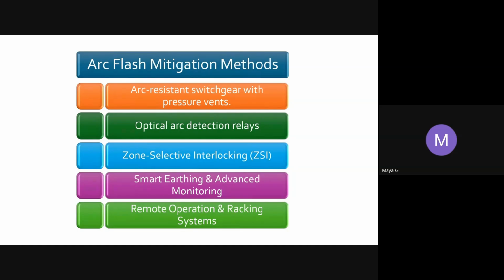These are the procedures to be followed. So for the arc flash mitigation process, we have done with grounding, bonding, and the barriers, and finally the mitigation methods for arc flashes. There are different methods. The five methods displayed are arc resistant switchgear with pressure vents, optical arc detection relays, zone selective interlocking, ZSI, smart earthing and advanced monitoring, and finally the remote operation and racking system.